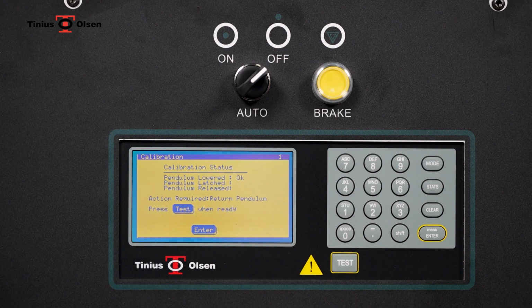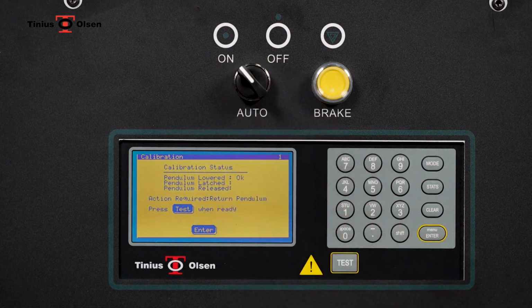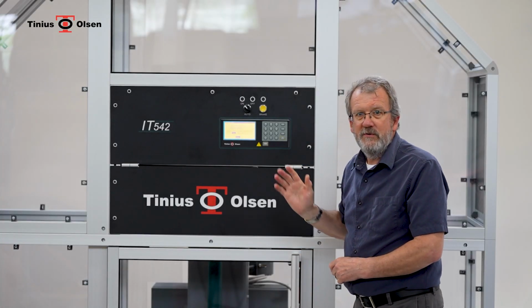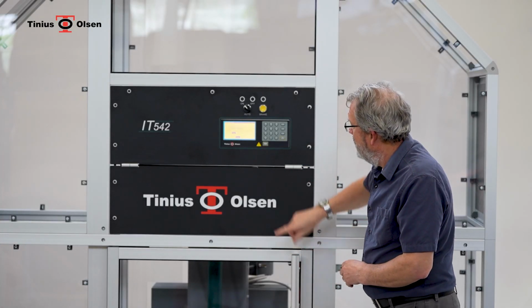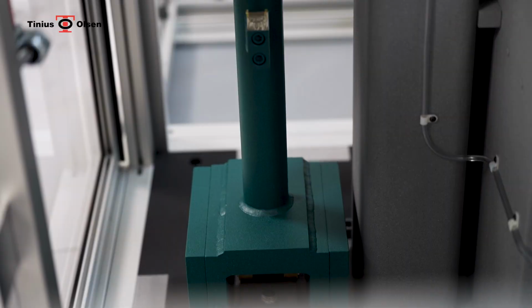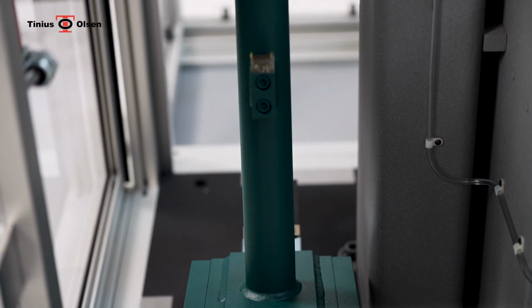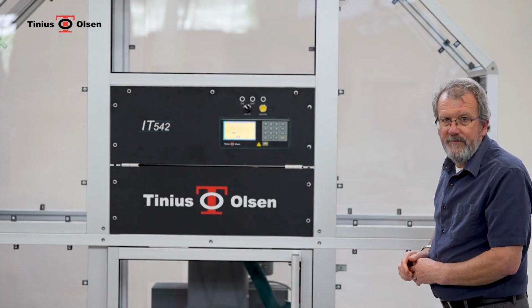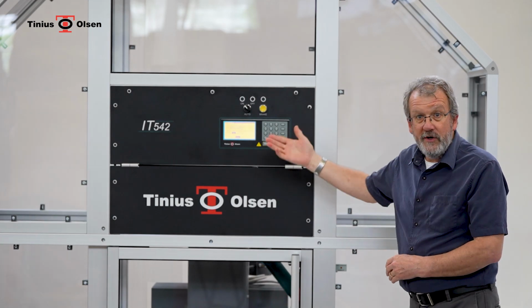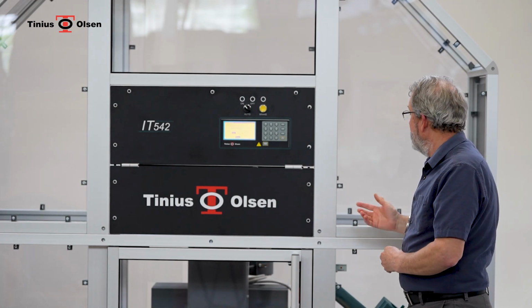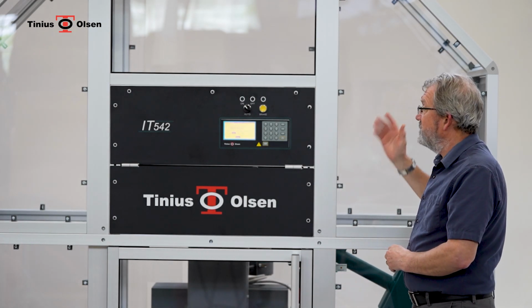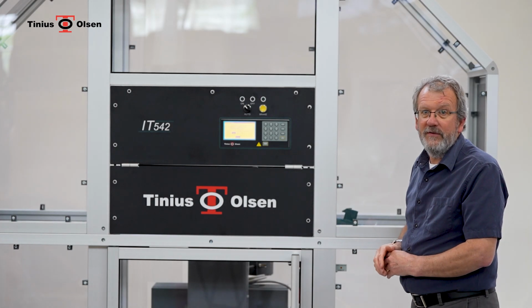Press test when ready. At this point, the machine needs to be turned on to automatic to ensure that the pendulum will relatch. When we press the test button, the motor will grab hold of the pendulum and drive it up into the latch position. The encoder is recording the position of the pendulum during its rise, and once it latches, it will know exactly the angle that it is at.